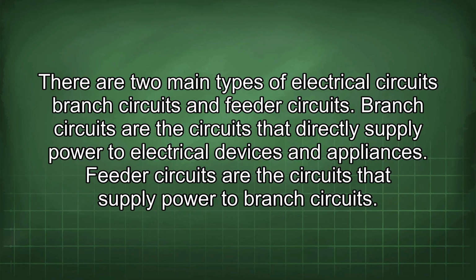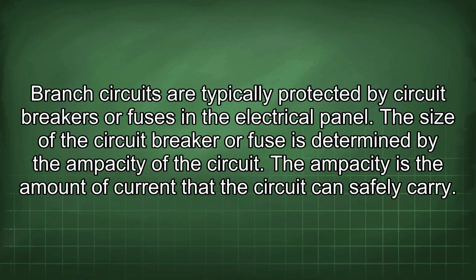Branch circuits are the circuits that directly supply power to electrical devices and appliances. Feeder circuits are the circuits that supply power to branch circuits. Branch circuits are typically protected by circuit breakers or fuses in the electrical panel. The size of the circuit breaker or fuse is determined by the ampacity of the circuit. The ampacity is the amount of current the circuit can safely carry.